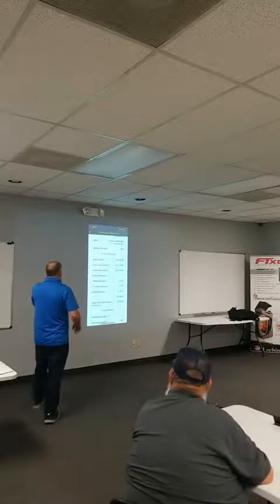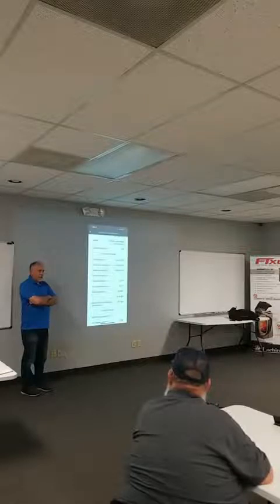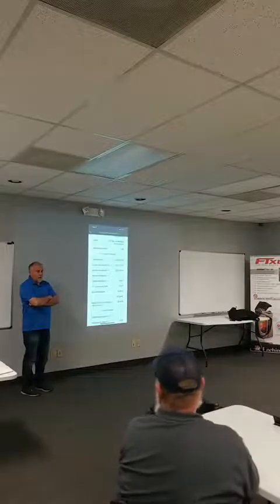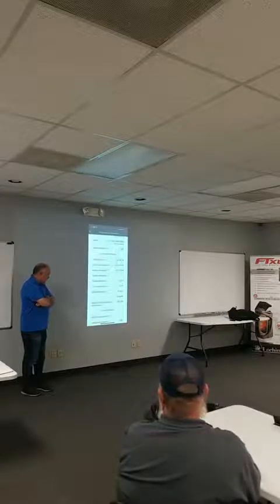There's the temperature split. Now, here's a good question for you. Target temperature split on this machine is 13.5 degrees, right? 13.5. Think about that for just a minute. Well, part of it is because we set the airflow a little high on this. This is running 1,500 CFM airflow, which is almost 4 tons of air, when I benchmarked the system. So I'm saying it's more set up for almost a desert climate, 450 CFM per ton or so. And the other thing is that if we cleared that benchmark out, it would probably look for a higher split. But the biggest thing is just the high airflow. So we need to lower the airflow to get the split. But when we benchmarked it, it locked that split in as being okay.